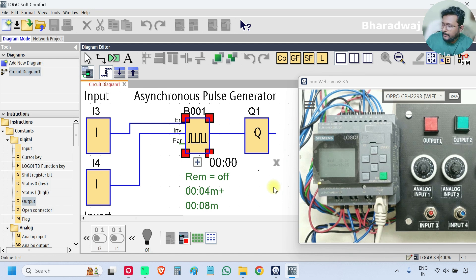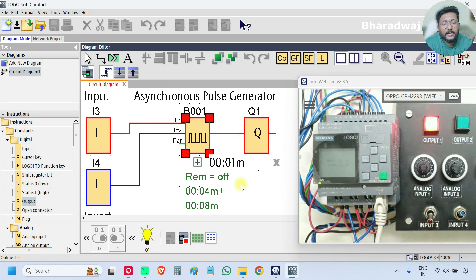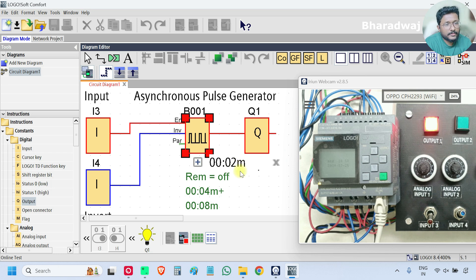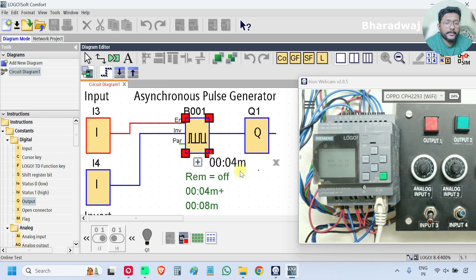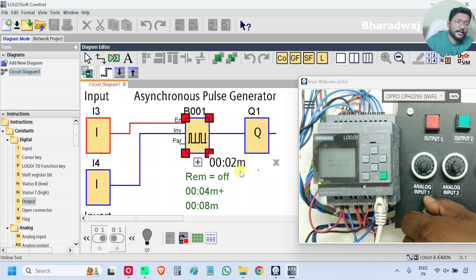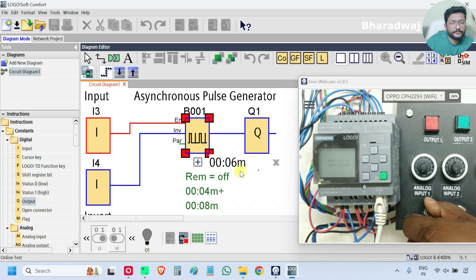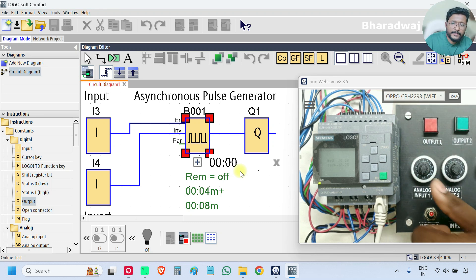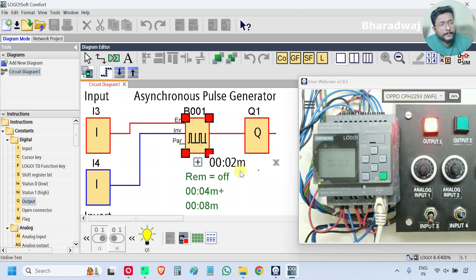Now I will turn on the input I3. The output will be on for 4 minutes and off for 8 minutes. Again it will repeat. This is a continuous pulse generator — continuously it will generate pulses based on our setting, and the input must be on. If the input is off, the output also will be off and the timer will be 0. The input must be on, then only the pulses will be generated.